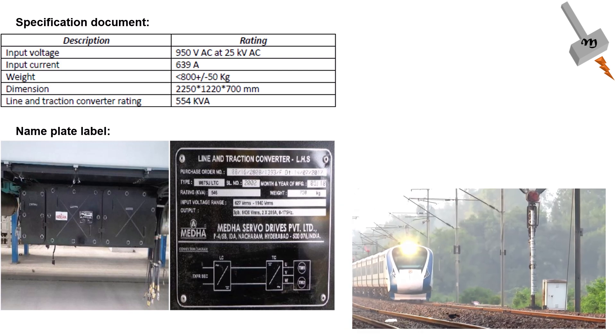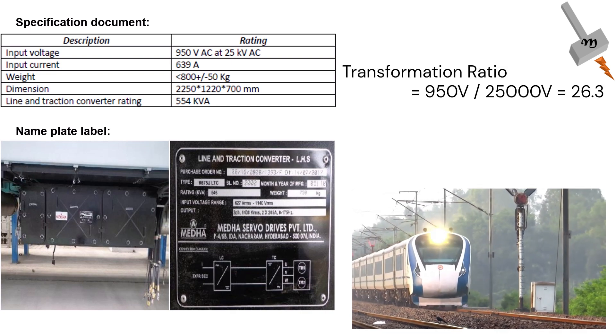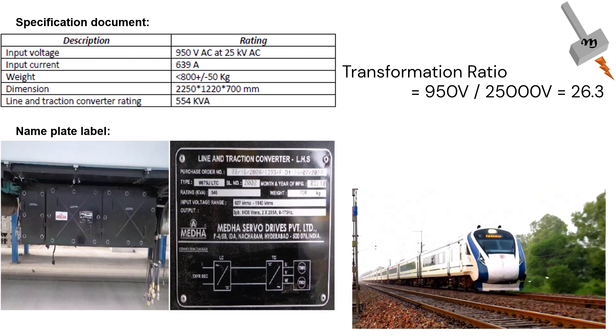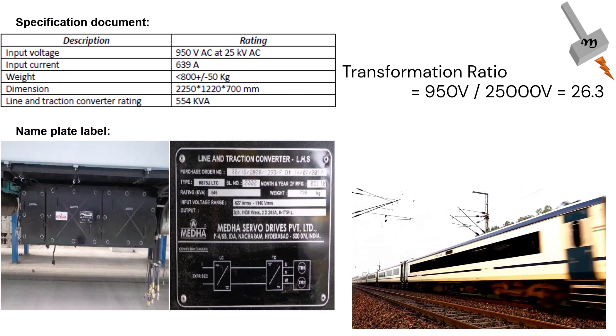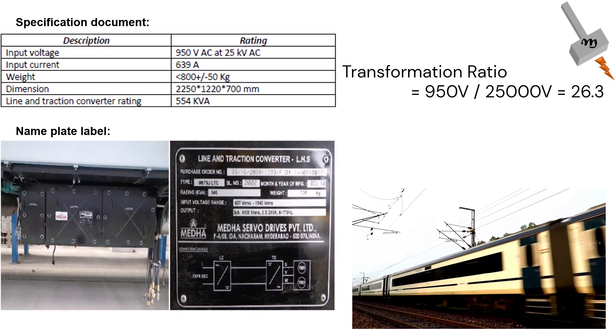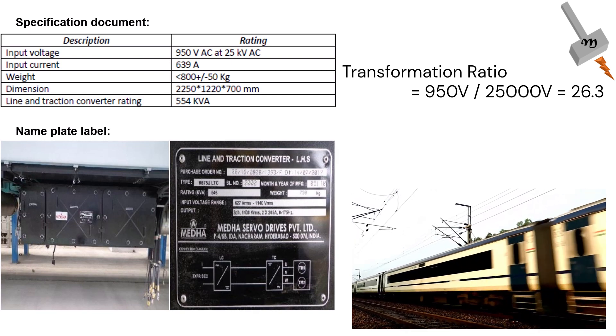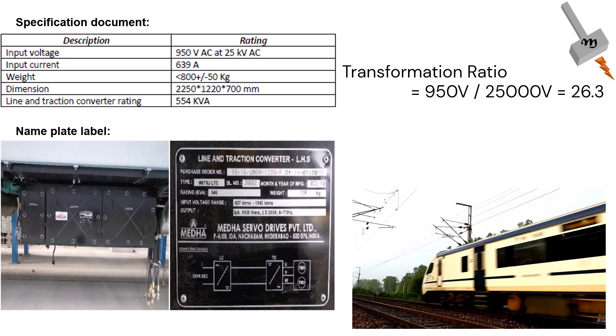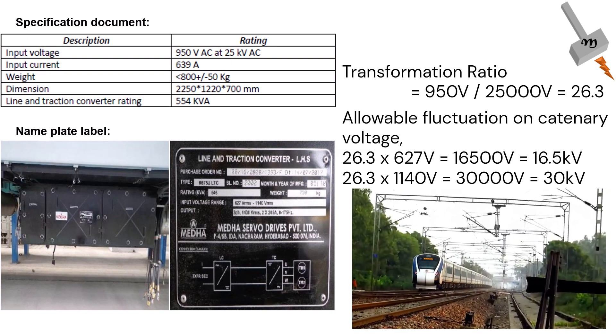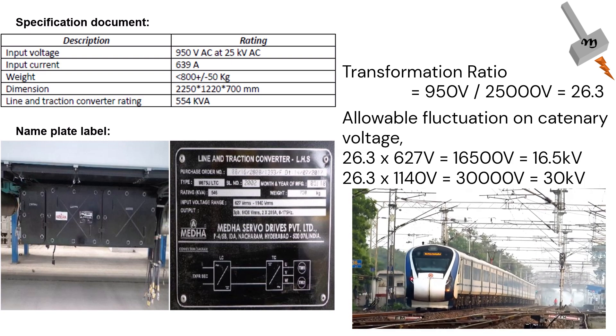Moving ahead, if we apply the transformation ratio on the converter input voltage of 950 volts and standard traction supply voltage of 25 kV, we can find the winding ratio of the transformer is 26.3. If applied to the input voltage range given in the nameplate, which is 627 volts to 1140 volts, we can find the fluctuation in the catenary supply voltage is from 16.5 kV to 30 kV.